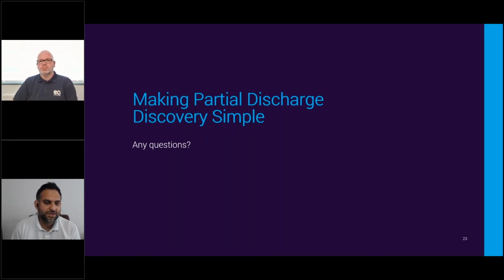But with the UltraTEV Plus instrument, for example, it locks onto the phase frequency. So when you are within the substation, you look at the phase plot, and that quite quickly allows you to differentiate between whether what you're picking up is external noise or genuine PD. So there are built-in features within the instrument that allow you to differentiate between background noise and partial discharge activity.